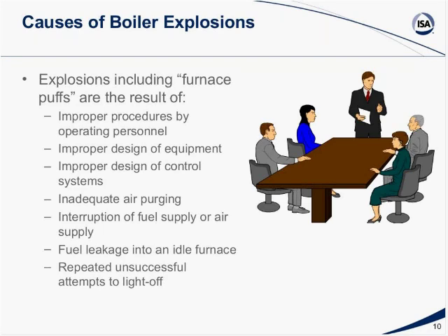Fuel leakage into an idle furnace can also create an explosion, particularly if there are hot spots in the system, or if they try to start an ignition and there's a fuel-rich system in the boiler. Repeated unsuccessful attempts to light off have been a really common problem in the industry, where operators cannot get the system to light off, and they keep trying and trying again until they have an explosion. If you cannot solve the problem, you need to shut down and determine what the problem is before you try to start up again.